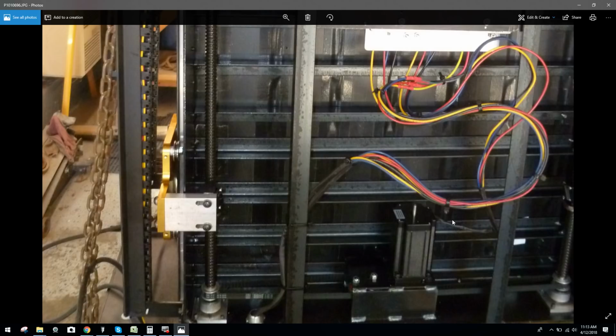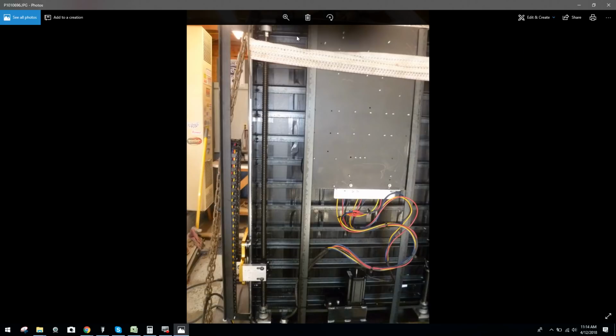This is silly. The vendor chose those drives because, once again, they either wanted to have a way to vary the price and adjust it to what they saw fit, which I truly don't believe. I personally believe it's ignorance because I can't figure out why they would do that. They made more work for themselves. And you can tell from how they wired the system, it didn't make sense to choose not shielding everything, using quick connects, all the easy way outs. Hell, even your motor connectors here, the motor wires. Let's see if I can zoom in again.